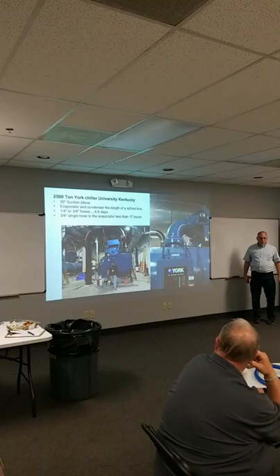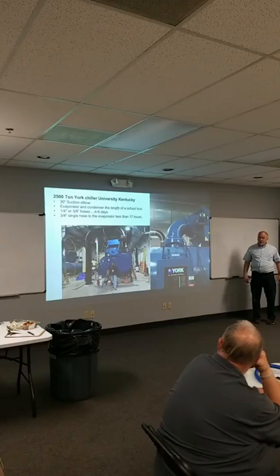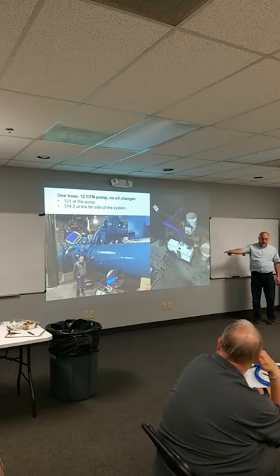That was pretty typical for these guys to do, 4 to 6 days. We went out with a single true blue hose and we had it down in 17 hours. Now the manufacturer called for 1,000 microns, right? And I started this in the afternoon, I came back. We were at 121 microns at the pump and 300 microns at the far end of the barrel.